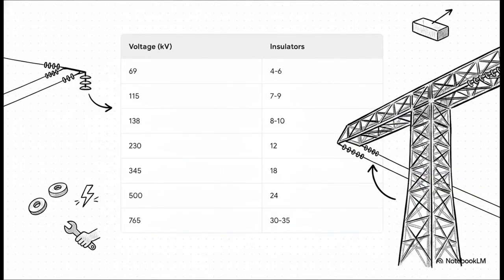You can see how this works because the grid scales directly with power, and so does its defense. Take a relatively lower high-voltage line at 69 kilovolts; that might only need a string of 4 to 6 insulator discs. But as the power scales up, the defense has to step up too. To stop a massive 765 kilovolt surge, engineers have to chain together up to 35 individual insulator discs, which dramatically increases the size, weight, and cost of the entire tower structure.